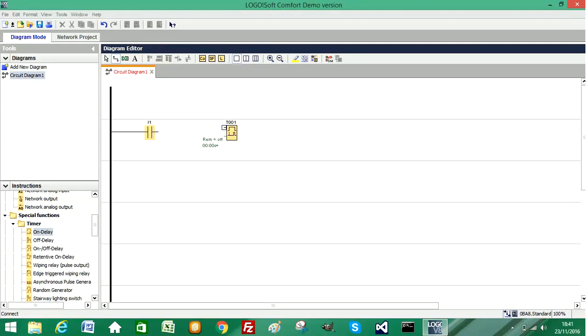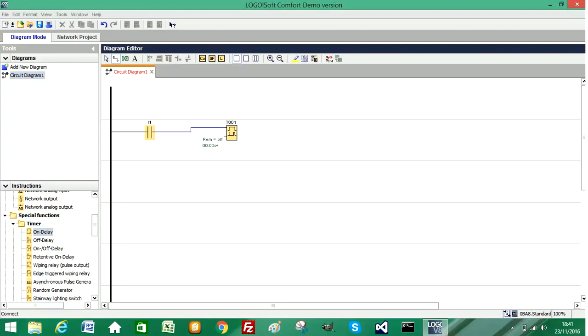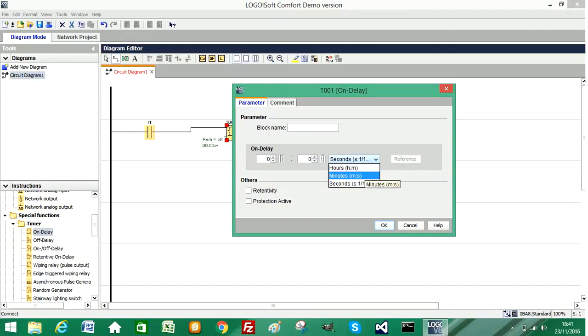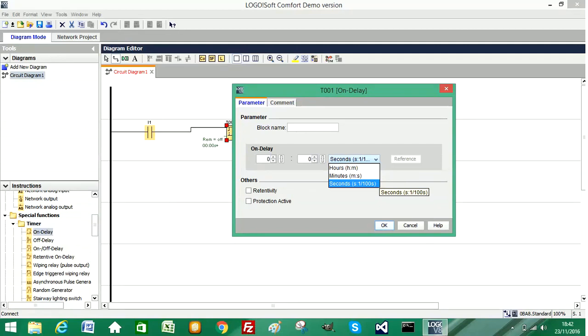So I'm going to wire this to our normally open contact and I'm going to right click on the block and select the block properties. There are three options for your time configuration: hours and minutes, minutes and seconds, or seconds and milliseconds. I'm going to choose the third option for seconds and set the delay to three seconds.